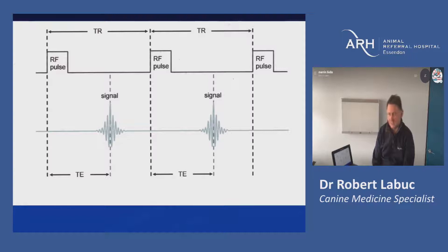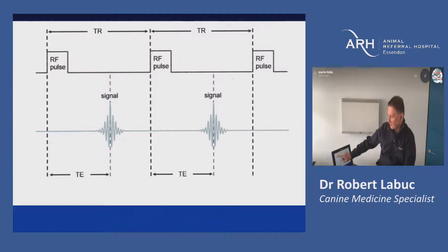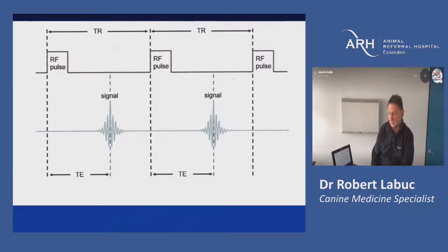This representation is a graph showing that if we have a pulse of irradiation, we produce a signal recorded by the MRI itself. The time between the pulses is called the TR time, and the time from the pulse to the actual echo of the hydrogen atoms moving back is called the TE time. These are manipulated to make images of different quality and to provide different types of contrast when looking at the images.